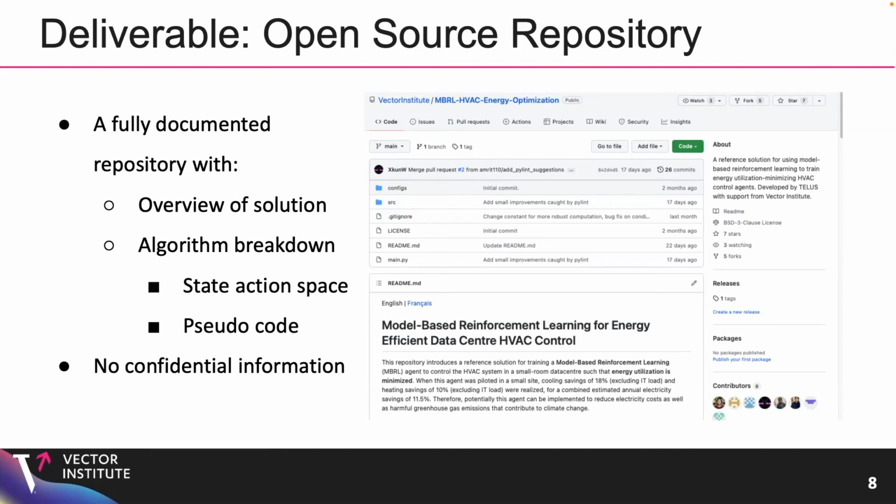There are 3 different types of negative rewards associated with the temperature control environment. A power consumption reward that penalizes the agent for consuming power, a device start reward associated with turning on the compressor or the free cooling device, and a temperature violation reward if the agent goes into a state that exceeds the allowed temperature range. The temperature change of each state action transition is determined by the state transition parameters.